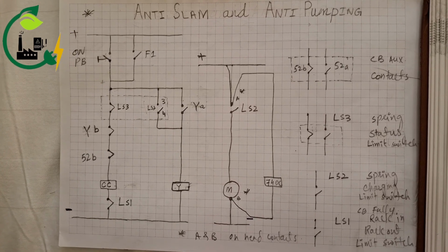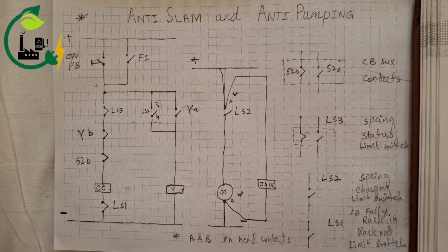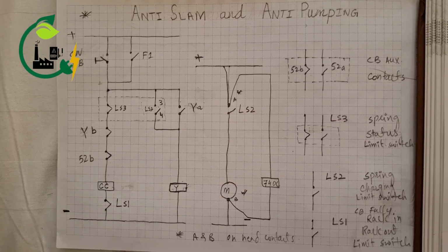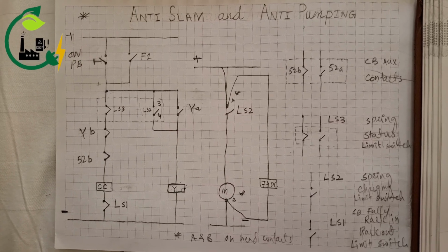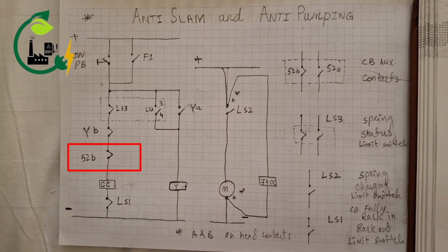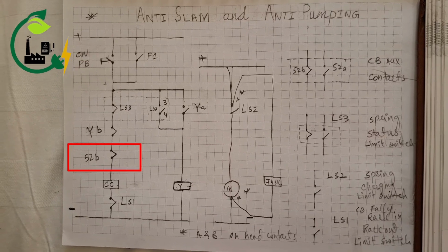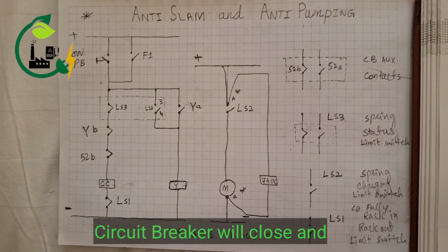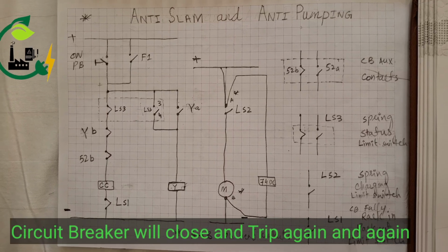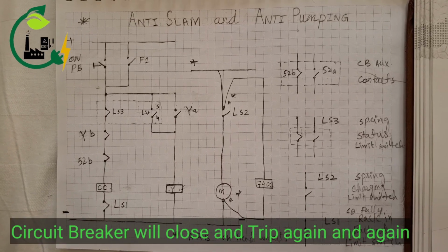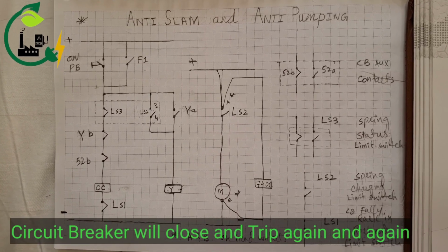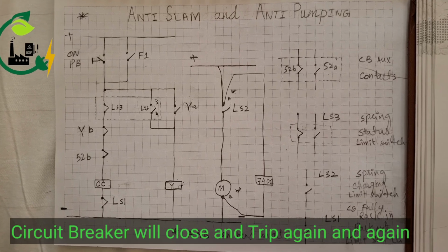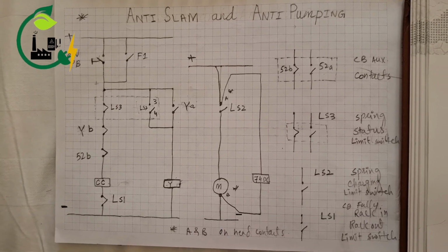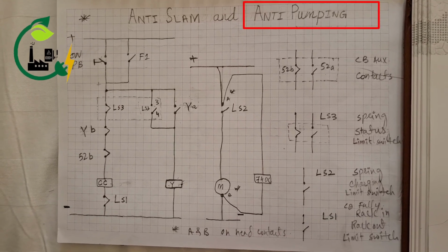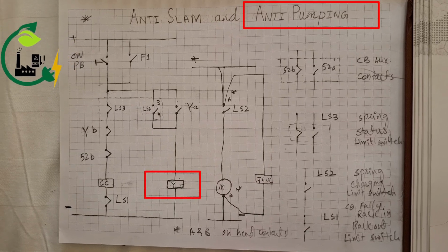So then what will happen? The circuit breaker will be tripped due to protection and will close again because supply is available, since 52B is now normally closed. In that case the circuit breaker can be damaged, because opening and closing commands are both available on the circuit breaker. The SF6 gas will have no time to rebuild and the circuit breaker can be damaged. So to prevent this issue, we use the anti-pumping relay.